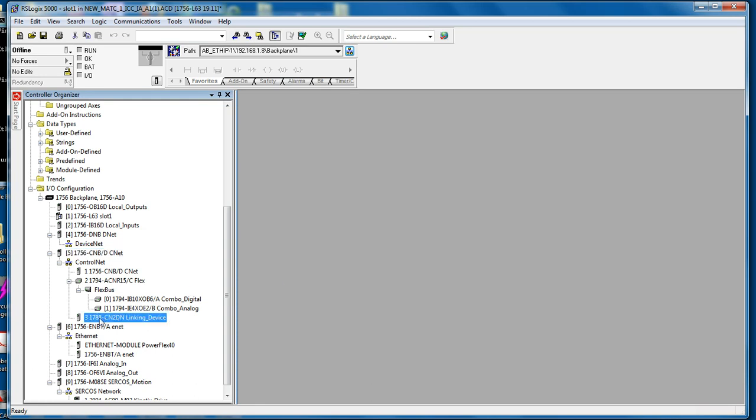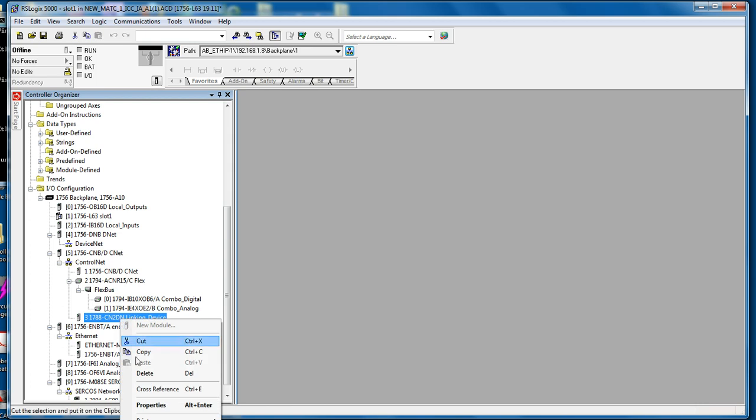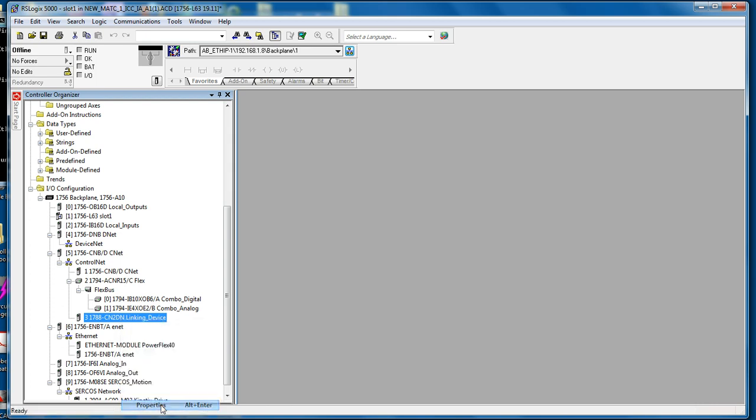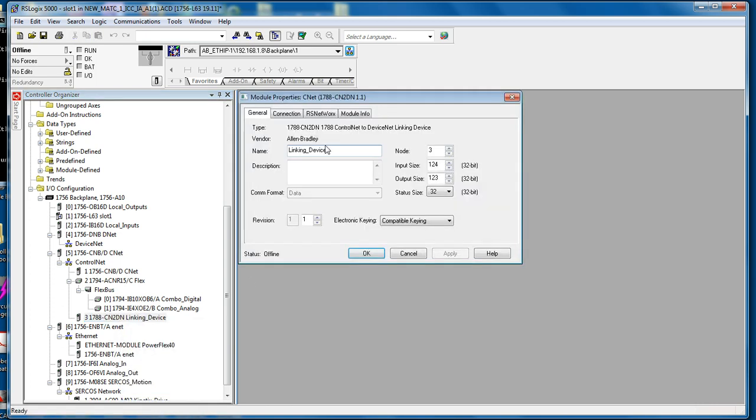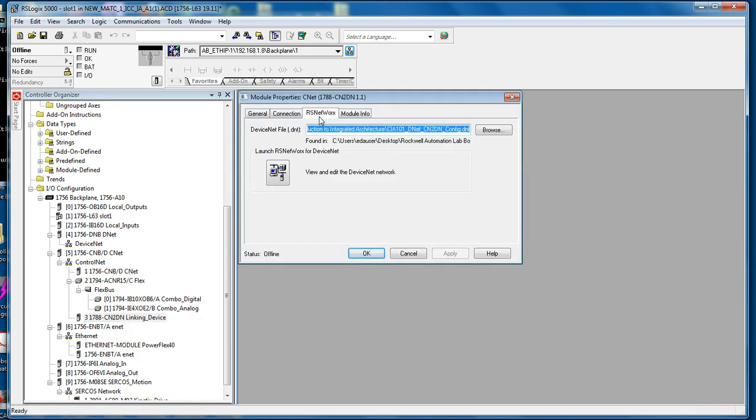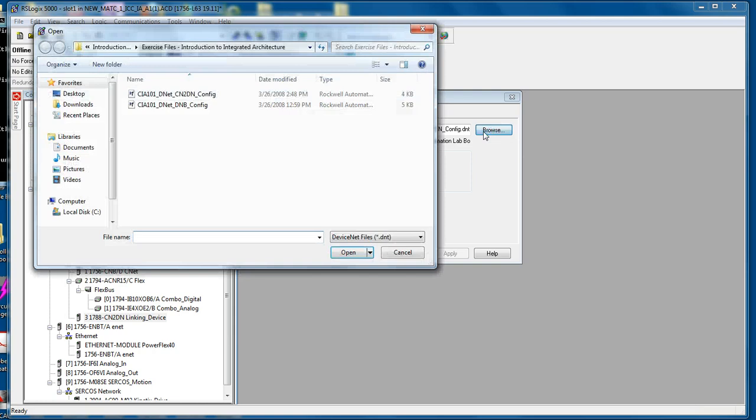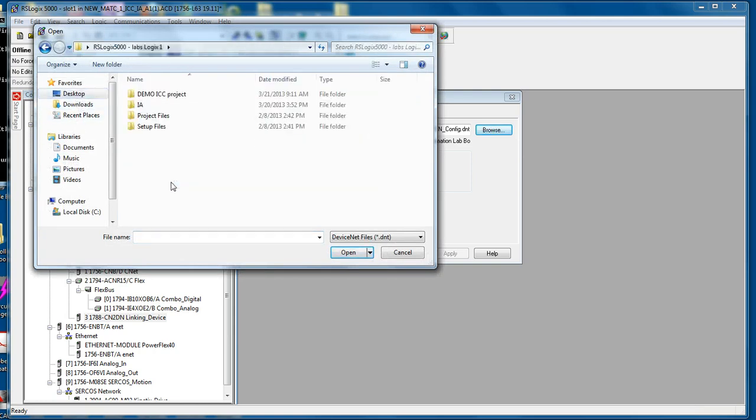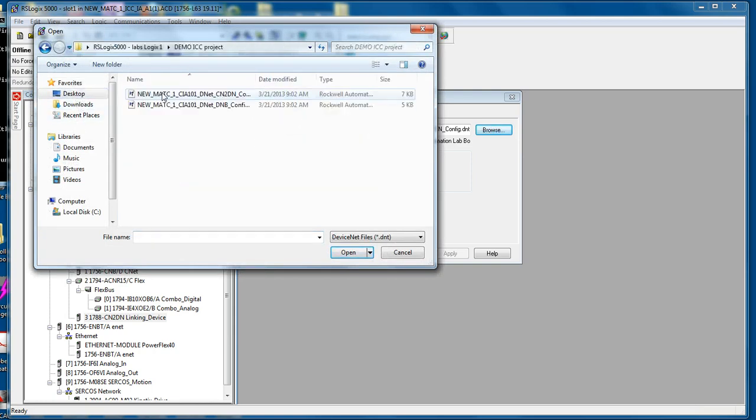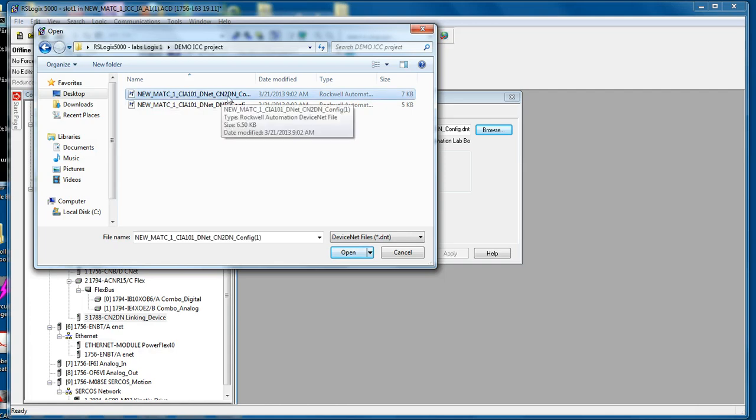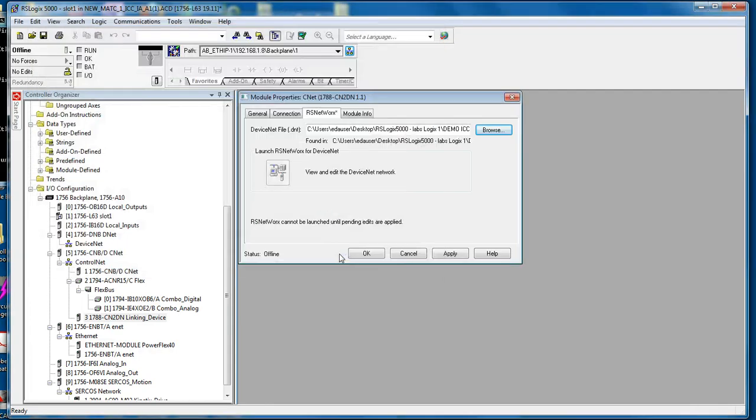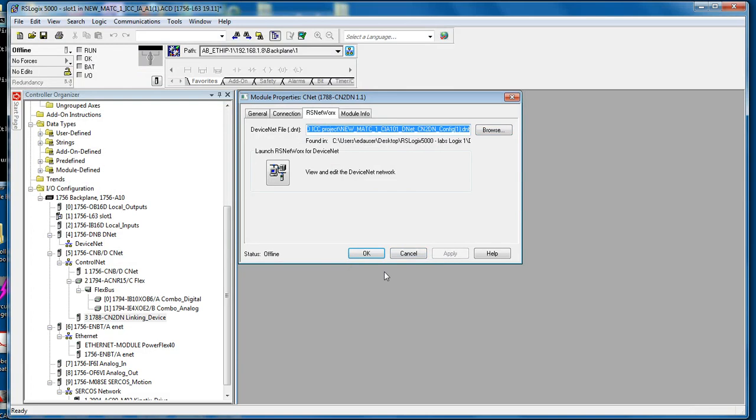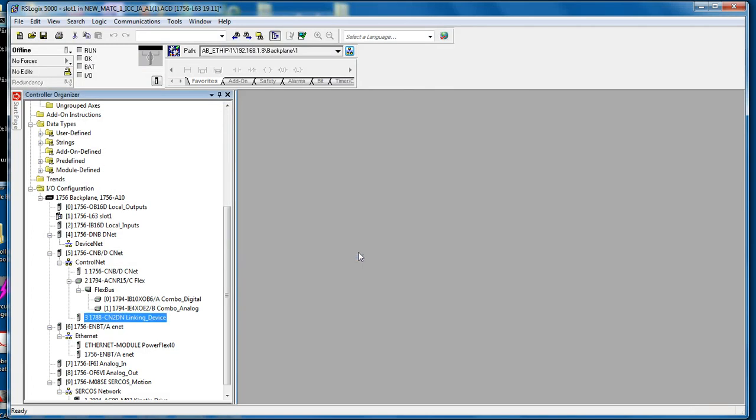Then the last configuration file is here under control net, the linking device. Right click the linking device, properties, go to the RSNetWorx tab, click browse, find the file you downloaded. Here be sure to select the CN to DN configuration file. Click open, apply and OK.